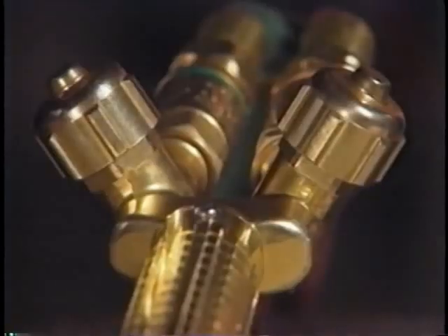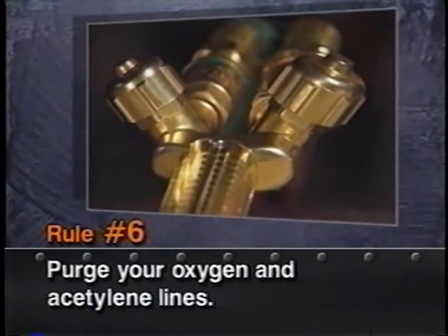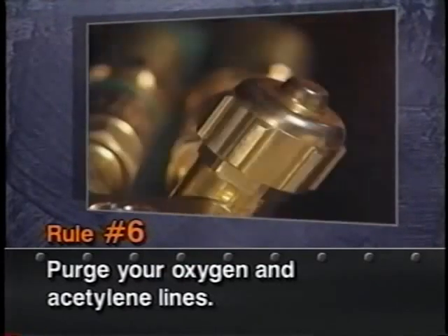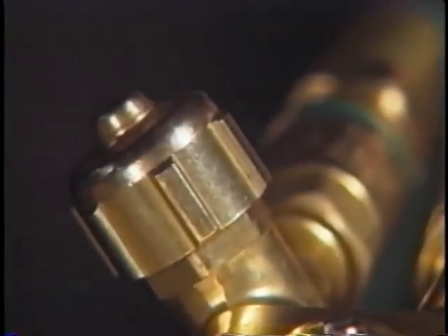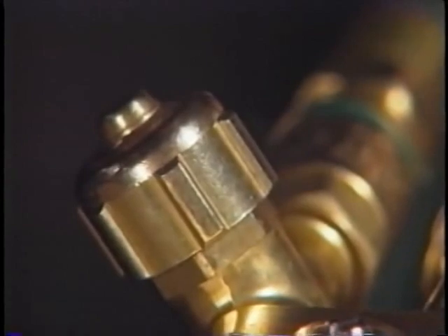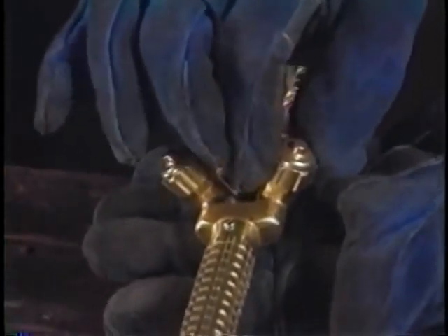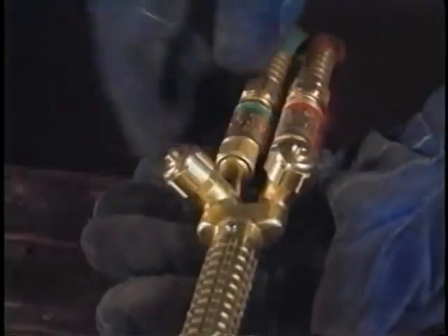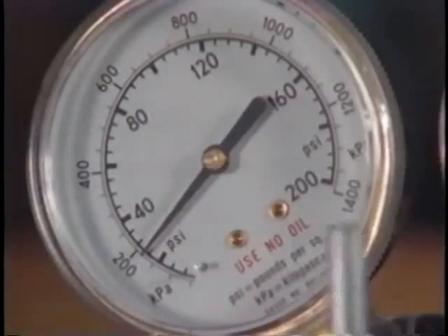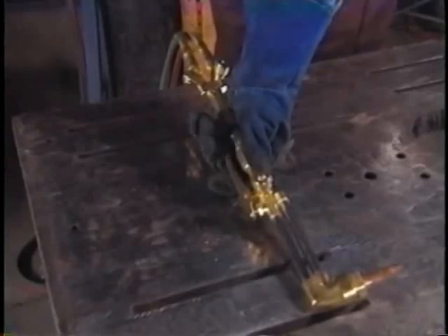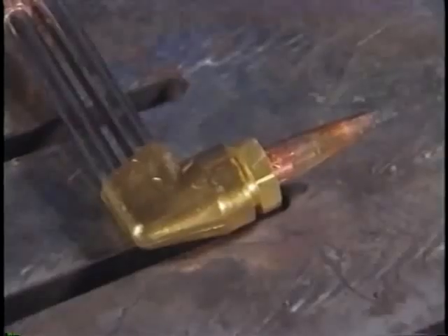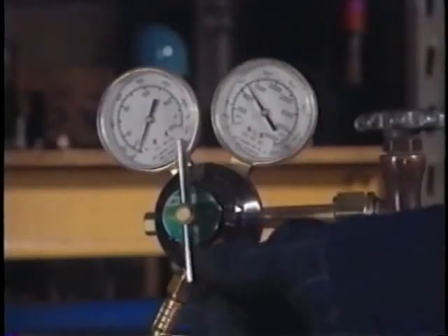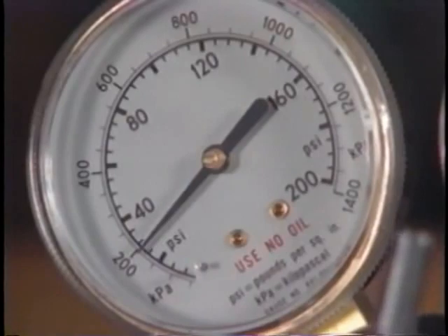Rule number six: purge your oxygen and acetylene gas passages individually before lighting the torch. It doesn't make any difference which you purge first, but it is good practice to have a routine. Start by purging the oxygen first — check that the acetylene valve on the torch is closed, open the oxygen valve and adjust the regulator to the correct operating pressure setting while the oxygen is flowing, then shut the oxygen valve off and repeat the procedure for the acetylene. This gets rid of any foreign gas in either of the regulators and sets your regulator pressure while the gas is actually flowing.